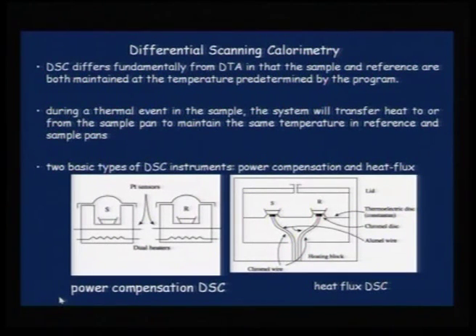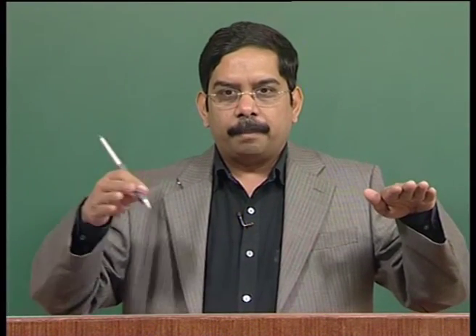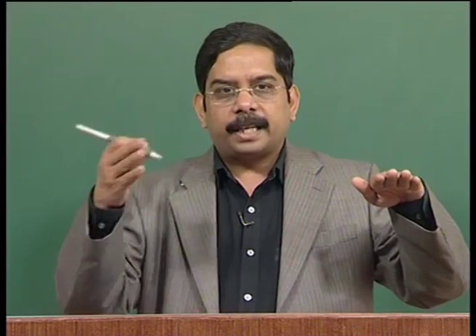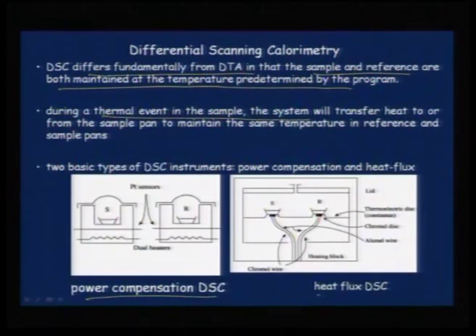In differential scanning calorimetry, the main difference from DTA is that the sample and reference are both maintained at the temperature predetermined by the program. At every temperature during the reaction — suppose the sample is at 100°C — both sample and reference are maintained at 100°C. Whatever change happens in the sample is recorded as an endo or exo peak. The system transfers heat to or from the sample to maintain the same temperature.